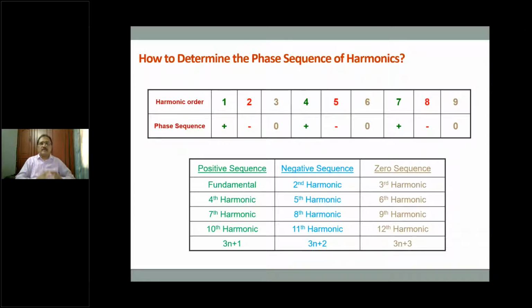They don't club together, but they will have the impact of negatively imposing a torque on the rotating machine. We will see a couple of slides on this topic. You will understand them when we go to them. Similarly, positive sequence will be 7, 7 plus 6, 13, 13 plus 6, 19, 19 plus 6, 25, 25 plus 6, 31, and so on. So up to 50, this is how they number the positive sequence, negative sequence, and zero sequence harmonics. Each type of harmonic has its own impact on the electrical network as well as on rotating electrical machines.